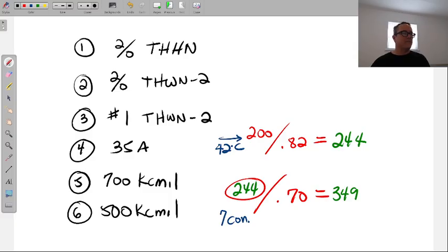Now the reality is, would you do this, would I put 7 current carrying conductors in 1 conduit if I'm already dealing with a temperature? Probably not. You can avoid it 100% by not doing that. Run 2 separate conduits, everybody in their own home. But these questions can show up. And here, it's just for fun, really. It is just to challenge you.